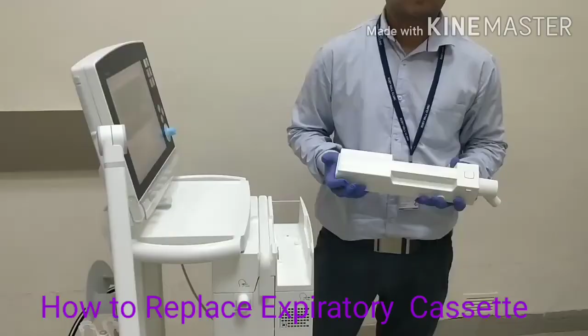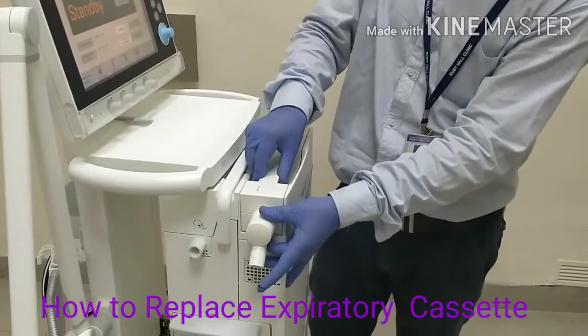After cleaning this expiratory cassette, now we will see how to fix it inside the ventilator. Here is one latch on this expiratory cassette. You have to match this with this rod at a 45-degree angle and just place it. Wait until you hear a click sound. After the click sound, your cassette is properly fixed, and this unit you have to push inside.